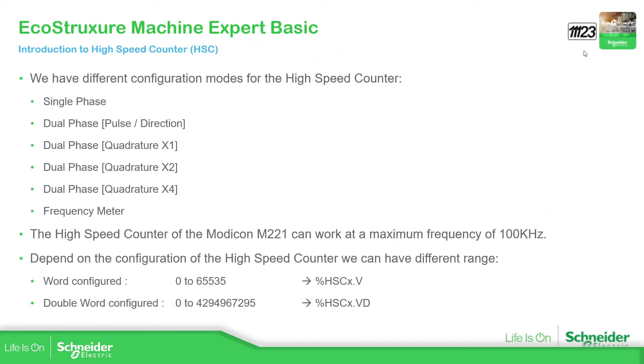Inside EcoStruxure Machine Expert Basic, we have the high-speed counter — HSC, which stands for high-speed counter — and there are different configurations. We have single-phase, which requires only one fast input, and then we have dual-phase, which can be used for encoders. We also have the frequency meter to read frequency.